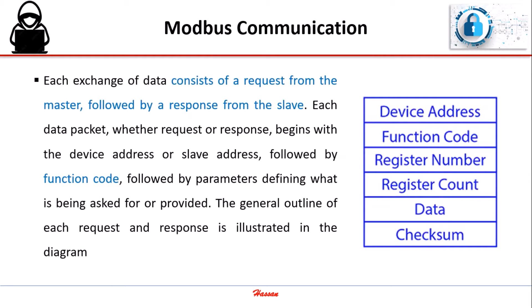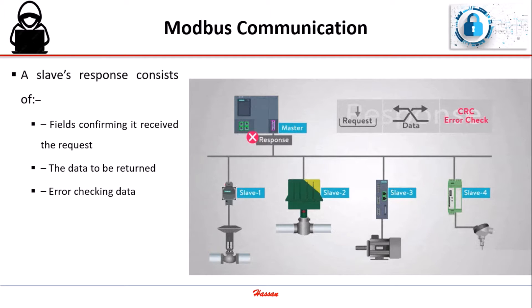Each exchange of data consists of a request from the master followed by a response from the slave. Each data packet, whether request or response, begins with the device address or slave address, followed by function code, followed by parameters defining what is being asked for or provided. The general outline of each request and response is illustrated in the diagram. A slave's response consists of the fields confirming it received the request, the data to be returned, and an error check field.